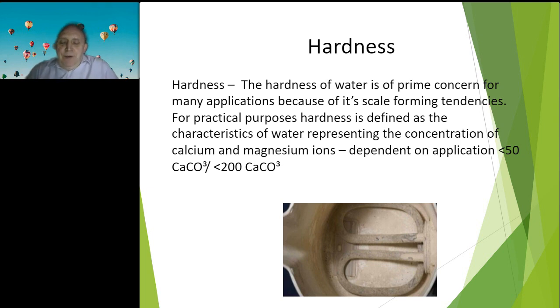So scale formation is a major no-no when it comes to decontamination. I've seen it in many washer disinfectors, and indeed I've lost many washer disinfectors before their end of life. So it's not cost effective, because a washer disinfector is an expensive piece of equipment. The last thing we want is scale to present within the internal chamber. We don't want it on the element, we don't want it on the devices. So within our technical guidance, depending on application, we have limits that are below 50, below 200. And we measure that routinely.